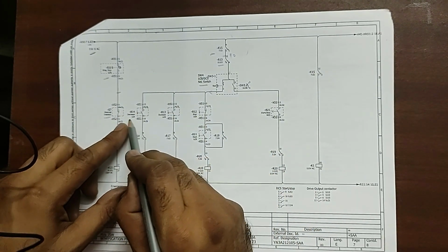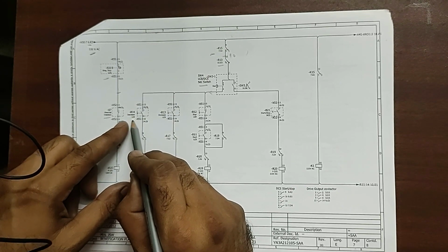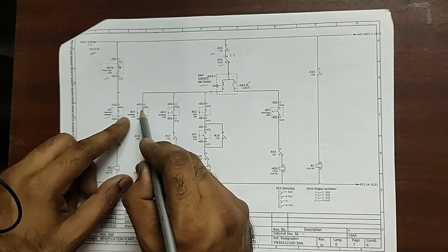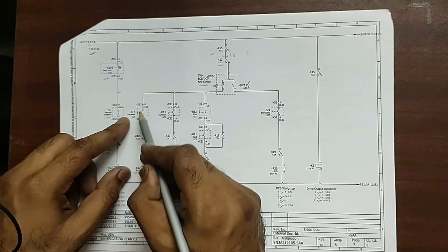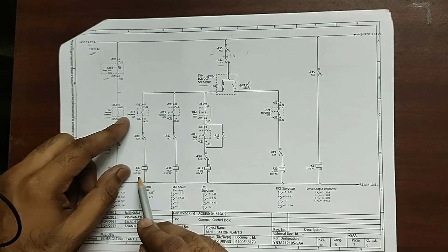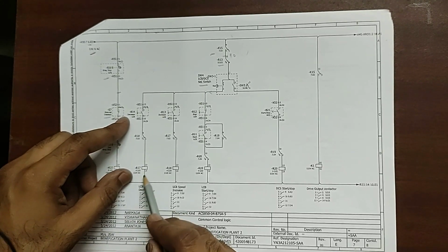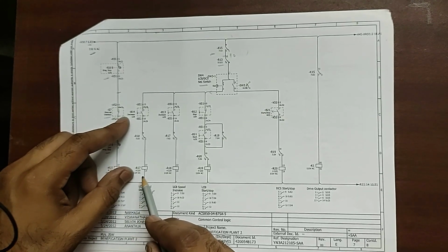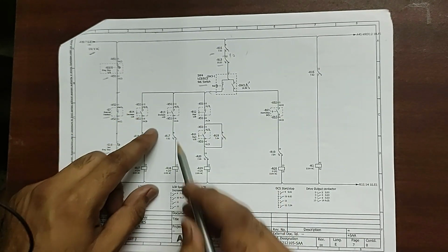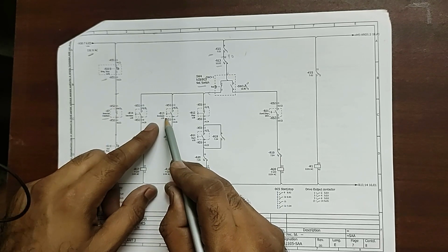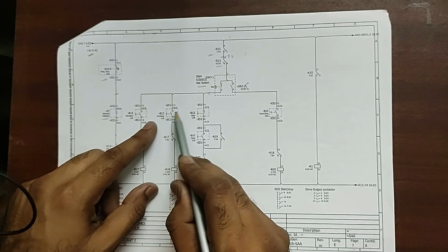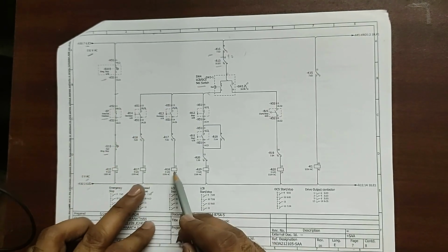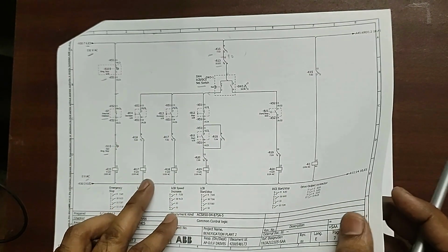We start with this one. This is LCB decrease. To decrease the speed, we have to keep this push button pressed, so that it keeps generating that volt, keeps generating this R17 relay high, and the speed will decrease. Similarly, for LCB increase, we have to press this so that the speed of the drive keeps on increasing. How it is connected, we'll see in the drawing.